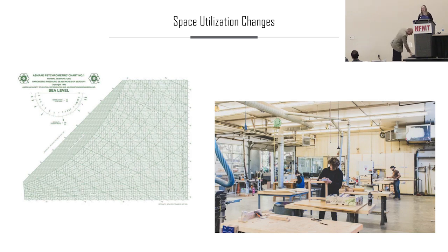As I mentioned before with the outside air, as your spaces change, aside from how much outside air you need to bring into the space changing, your temperature and humidity requirements may change too. As I mentioned before, this was the site I was talking about. That was a wood shop, a pretty large area where, for the woodworking equipment and finished products, certain temperatures and humidities were required to maintain the quality of that equipment and the products the students were making. However, when they transitioned this large space into a storage room, no one changed the programming, so it was still keeping those tight temperature and humidity requirements for really no need. So as you change spaces, try to make sure that if you are able to spread out those set points and reduce the mechanical heating or cooling, or even the fan speeds, any way that you can do that to take the load off the air handler a little bit will end up helping save you on your energy bills.